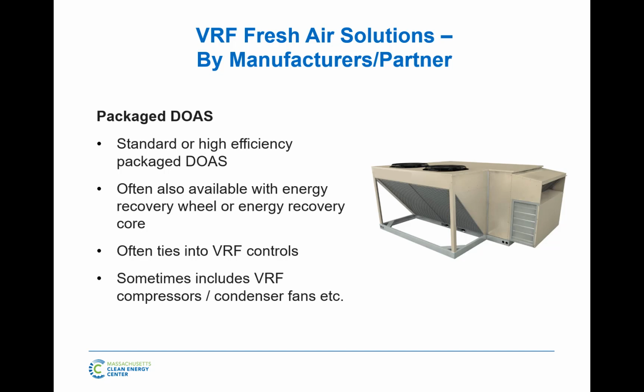Again, this does not handle heating and cooling, usually, if you have VRF. VRF does all heating and cooling because that's where a lot of the tonnage is, and we move that heat with little pipes throughout the building like we talked about. This is only sized in a building for the air required for the fresh air only. That's why a VAV system has big ducts. This just has small ducts because you're only bringing in 80 CFM in a room. Maybe a big room like this would be a few hundred CFM.